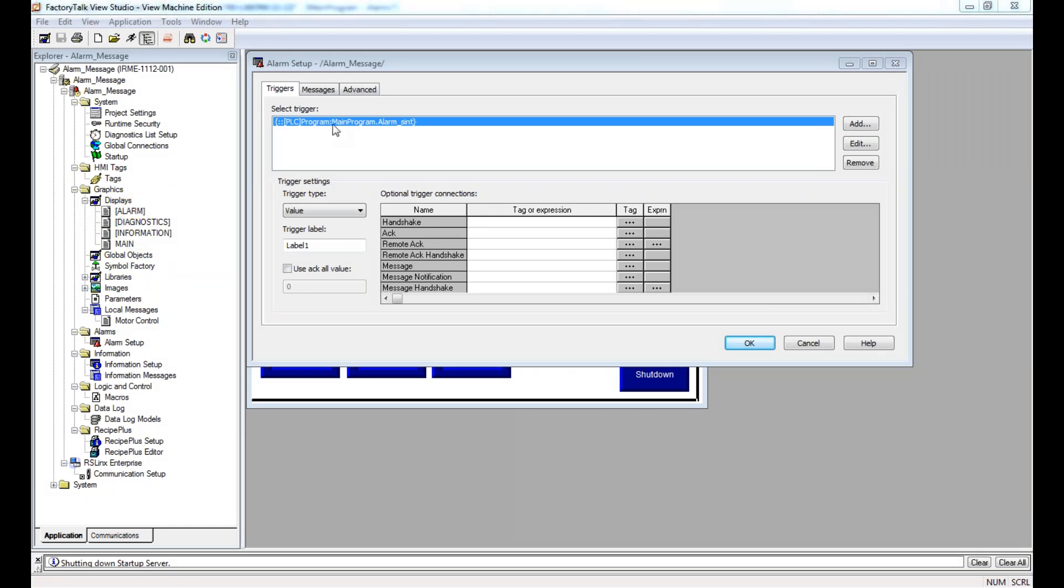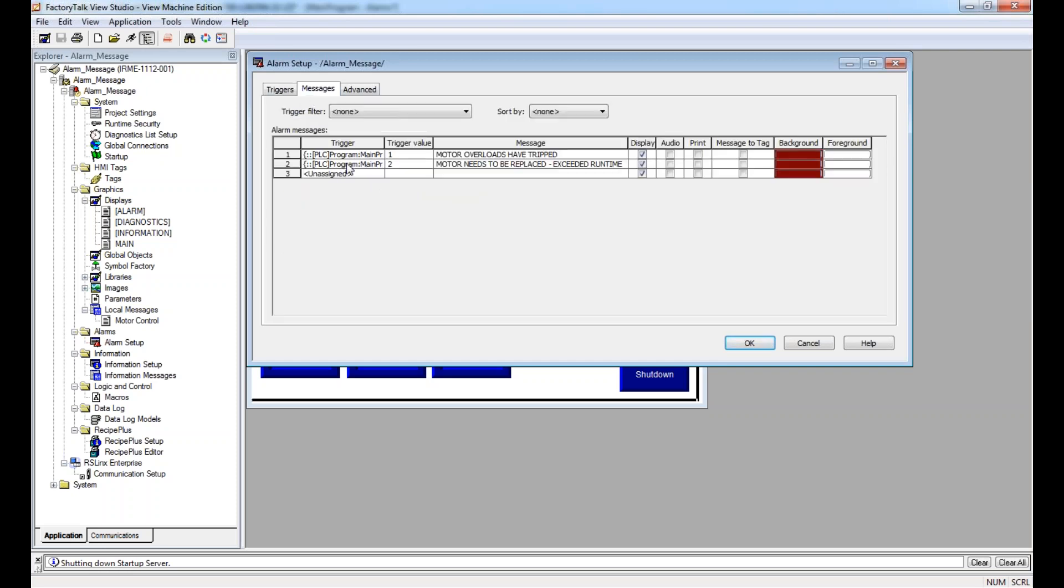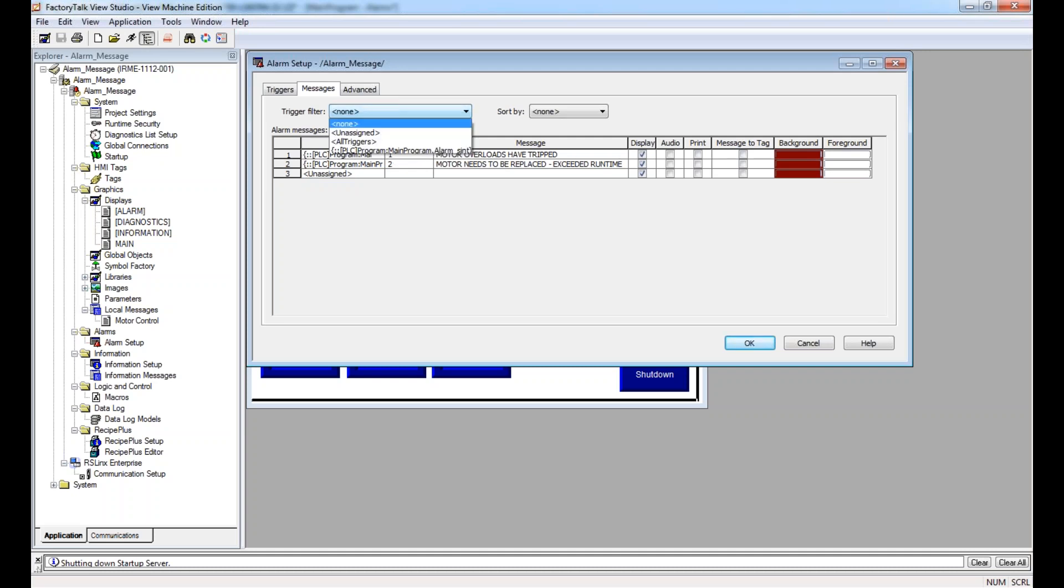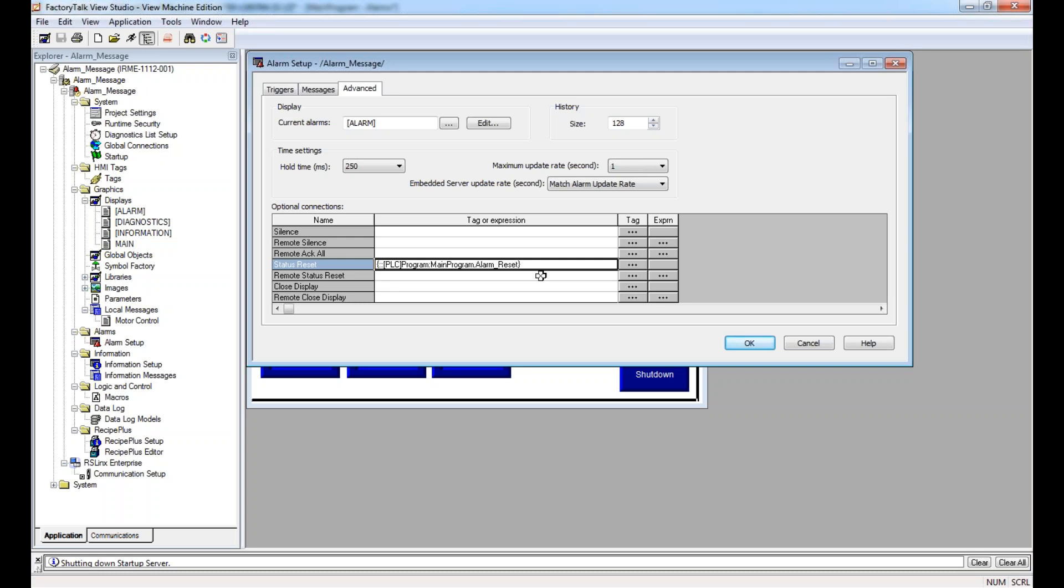Now, these values will say when this triggers, do this. So send a value to this PLC, send a value to this PLC, message this PLC. So that's what this is set up for right here. And I can do it as a value, a bit, least significant bit, depending. So I'm just going to do value. And here's where I set up my message. So I can highlight my trigger - all triggers unassigned, so if I have any trigger that shows up, it does something, and it will bring up this message. This is just like how messages work with the trip value, et cetera. I can filter out all my alarms, I can also sort by messages or trigger. Now, under the advanced tab, this is going to be displayed under alarms. But if I wanted to, I could set up a bit that it reads to reset my alarm from another PLC if I needed to. That's what this is saying. So if there's an active alarm on the HMI, this bit will trip that bit, clear that from an exterior source. So that's what these values are.